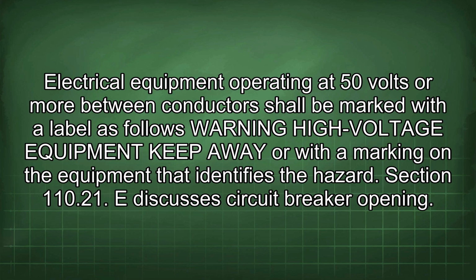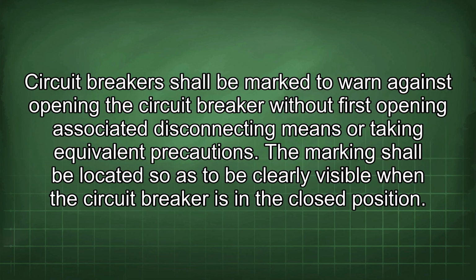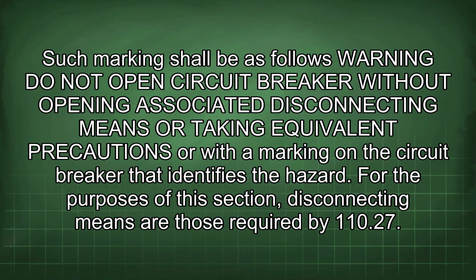Section 110.21(E) discusses circuit breaker opening. Circuit breakers shall be marked to warn against opening the circuit breaker without first opening associated disconnecting means or taking equivalent precautions. The marking shall be located so as to be clearly visible when the circuit breaker is in a closed position. Such marking shall be as follows: "Warning, do not open circuit breaker without opening associated disconnecting means or taking equivalent precautions," or with a marking on the circuit breaker that identifies the hazard. For the purposes of this section, disconnecting means are those required by 110.27.